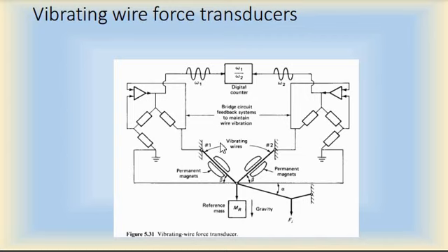Also, this system acts as a current to force transducer, and this force output keeps the wire vibrating, as it is the opposing force to the decay of the vibration. So, by proper design of this whole system, the feedback system can maintain a constant amplitude wire vibration at a frequency determined by the force carried by each wire.